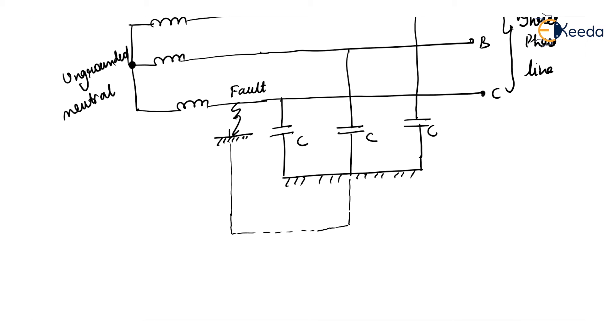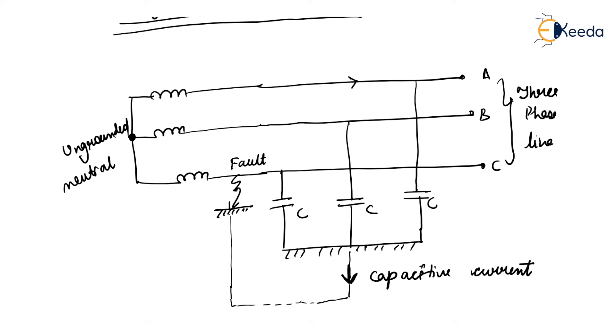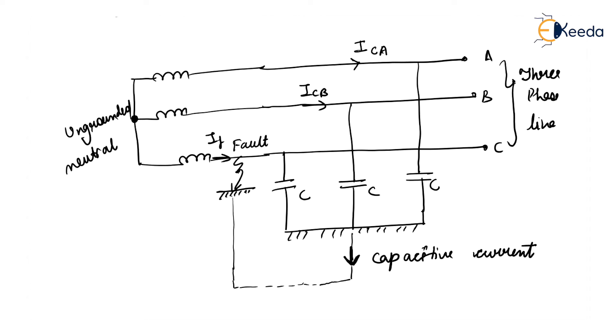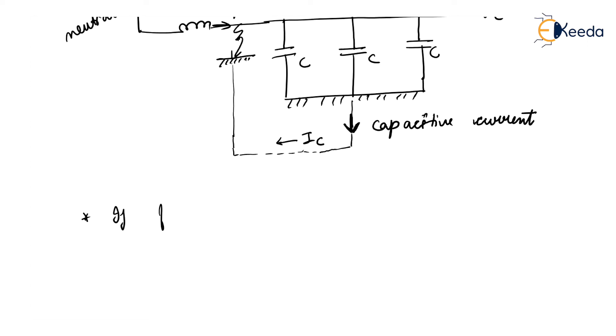When a fault occurs on any of the phases, the capacitive fault current ICA, ICB flows into the ground. The fault current IF and capacitive current IC — if the fault current exceeds 4 to 5 amperes, it is sufficient to maintain the arc.